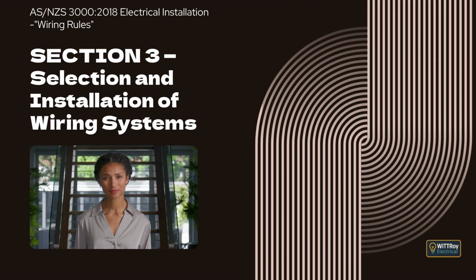Clause 3.11.4.5, Identification of underground wiring. This clause explains that underground wiring systems must be identified by orange marker tape installed above the wiring system. The marker tape must be positioned at approximately half the depth between the surface and the cable, or above any additional mechanical protection. Where cables are installed in rock channels, the marker tape must be placed directly above the wiring system before the concrete is poured.